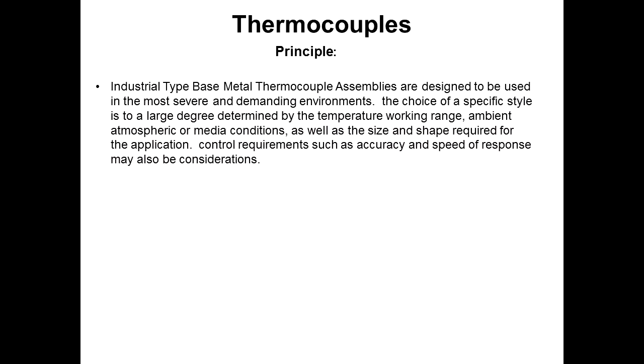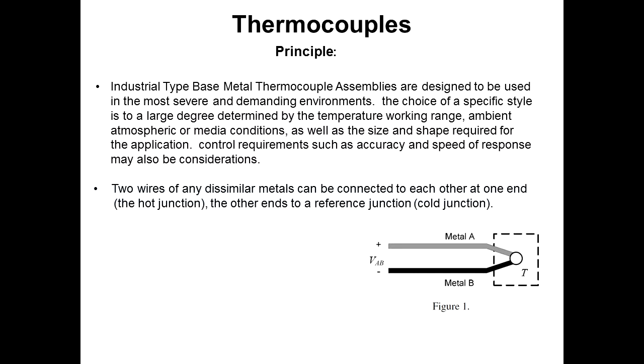Thermocouples most commonly are base metal alloys that are used in severe and demanding environments. The choice of a specific style is to a large degree determined by the temperature working range, ambient atmosphere, or media conditions such as the size and shape required for the application. Control requirements such as accuracy and speed of response may also be considerations. Two wires of any dissimilar metal can be connected to each other at one end, the hot junction, and the other ends to a reference junction, which is called the cold junction.